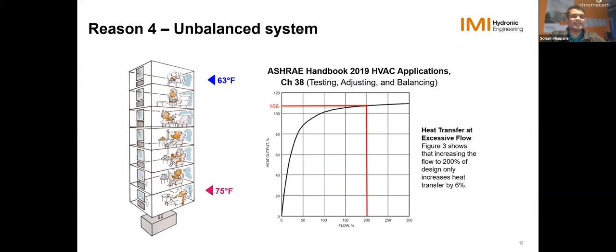So unbalanced system, again, if it's not balanced, you overflow your system, your water does not spend as much time in the coil, and you do not get enough delta T, and hence it's going to affect your chiller performance. So this curve here, basically, actually, let's start with this picture here. So what happens in unbalanced system, because you're overflowing, you're going to see the temperature gradient that I was talking about. Closer to the pump, you're going to have higher temperature and much lower temperature up top. And with overflow, you are also wasting a lot of energy, not just chiller, but also with pumps and all, right?